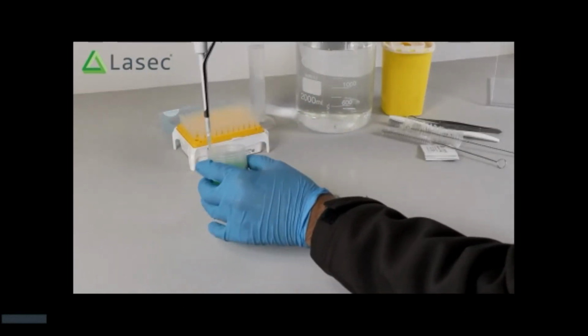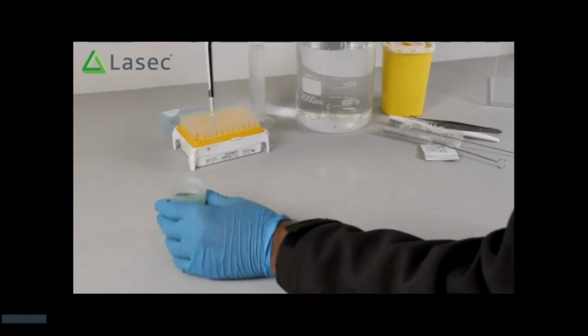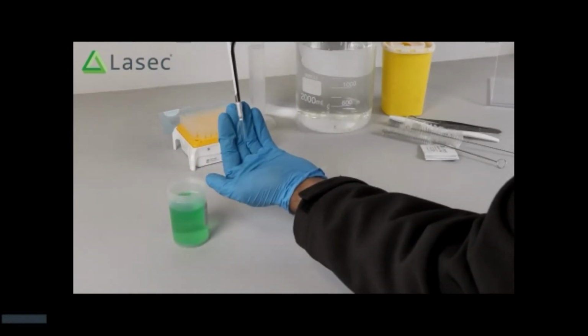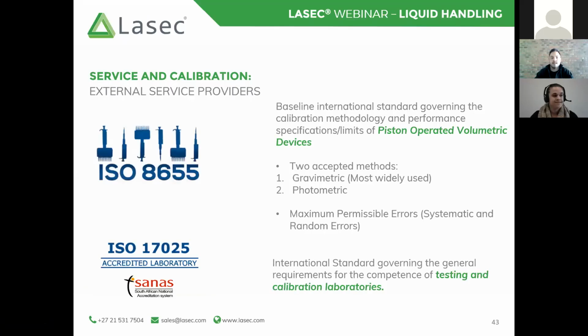Once you have reassembled the pipette, again, we go back to the inspection and we are going to want to make sure that it is functioning correctly once it's reassembled. So we would perform a leak test. Okay, and finally to wrap up, you guys have now essentially conducted your own preventative maintenance to the extent that an end user can look after their pipettes. Further to this, pipettes would then need to be serviced and calibrated by an authorized dealer of whatever pipette manufacturer you are using.